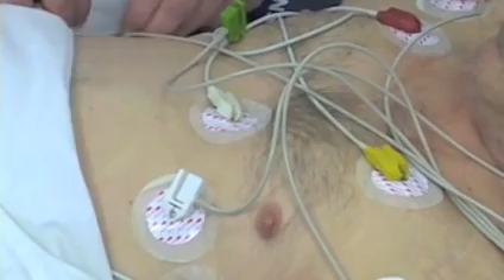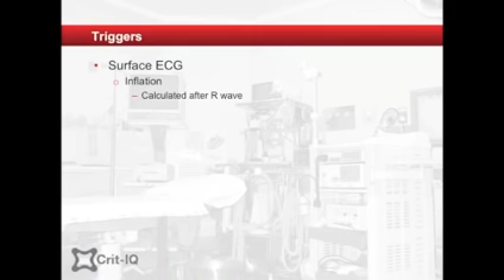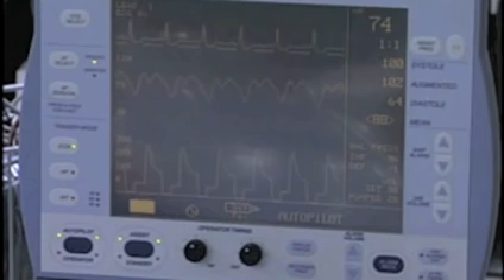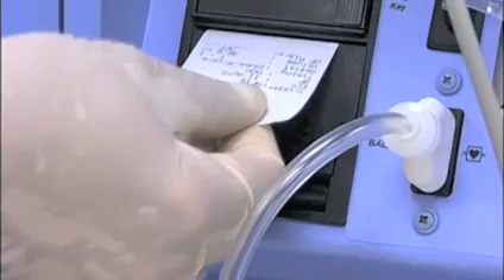Traditionally, the surface ECG signals have been used. Inflation of the balloon is calculated from the R wave of the ECG, and deflation is triggered after a defined period, if it's a regular rhythm, or by detection of a new QRS complex when the rhythm is irregular. Adjustment of the triggering is often possible when the balloon is found to be inflating or deflating at an incorrect time. This is usually detected by observation of the pressures in the aortic root taken from the end of the IABP catheter. These aspects, including intra-aortic balloon pump timing, will be covered in more detail in a later vodcast.